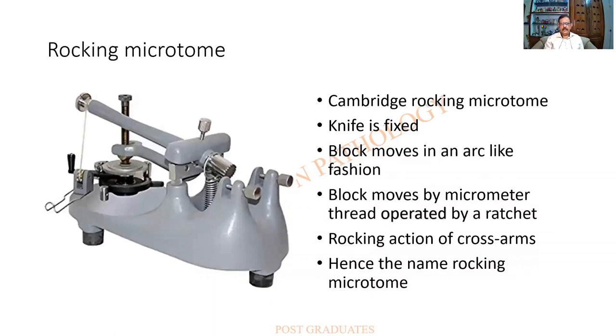The rocking microtome — I have tried to download the best pictures; students should carefully follow and apply the description to the pictures. This is a Cambridge rocking microtome. The knife is fixed; this is the knife holder. The block moves in an arc-like fashion, maneuvered by a micrometer thread operated by a ratchet. There are two arms called the cross arms, and they keep rocking — hence the name the rocking microtome.